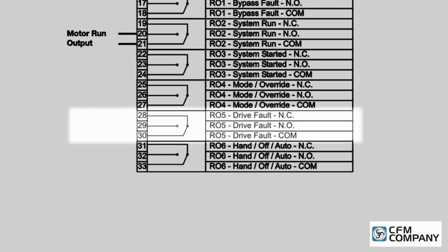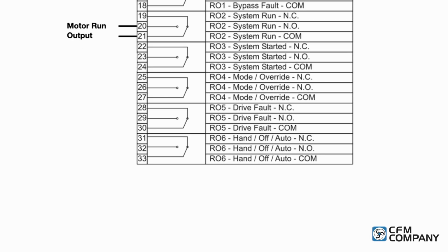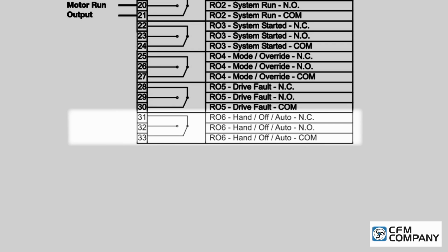Relay 5, terminals 28, 29, 30 is the drive fault relay. This relay is energized during normal operation and de-energized when a drive fault has occurred. Relay 6, terminals 31, 32, 33 is the handoff auto relay. This relay is de-energized when the bypass is in hand or off and energized when the bypass is in auto.